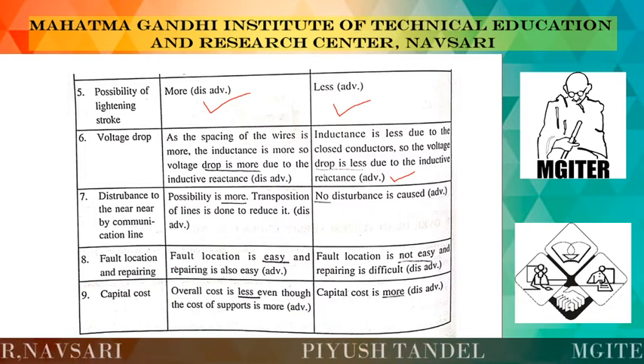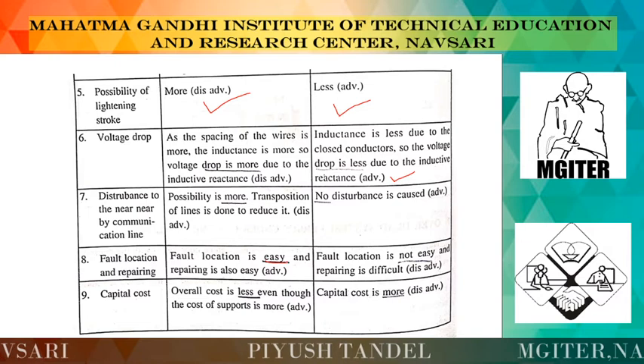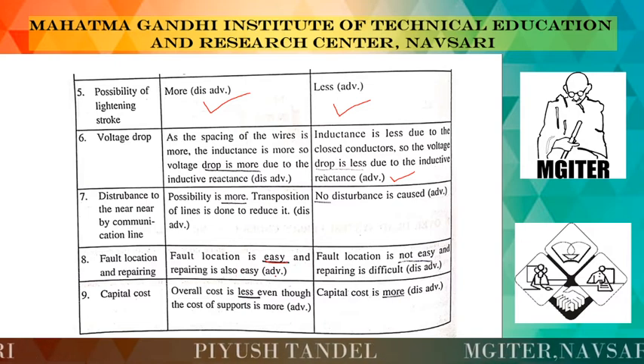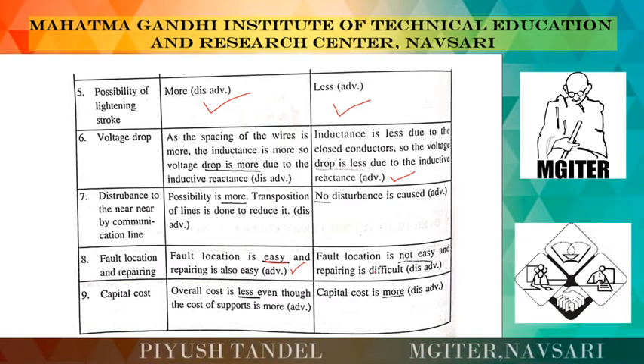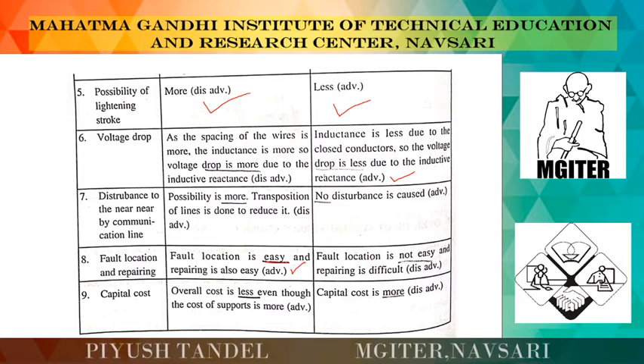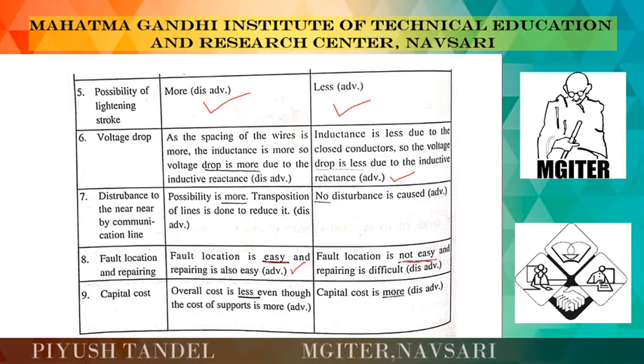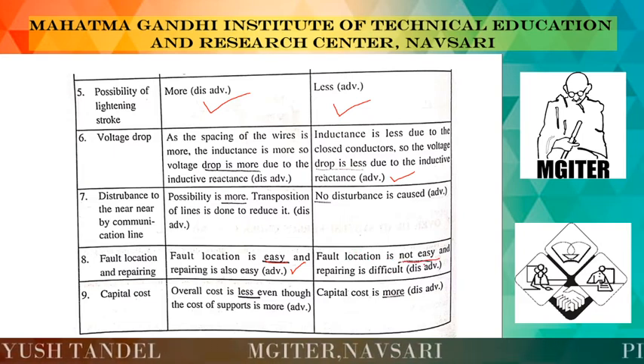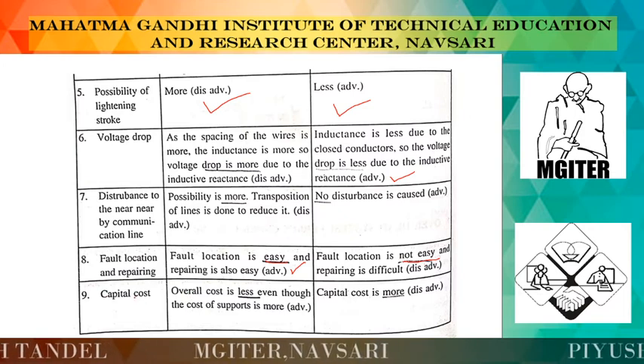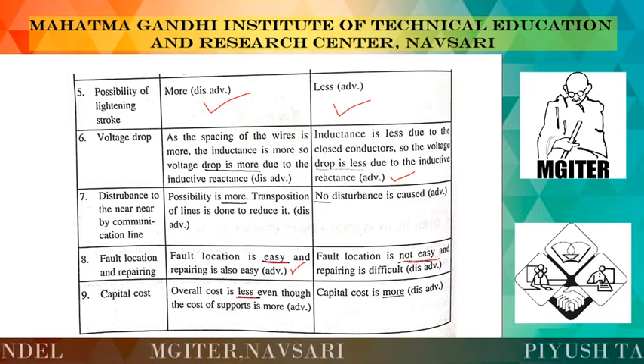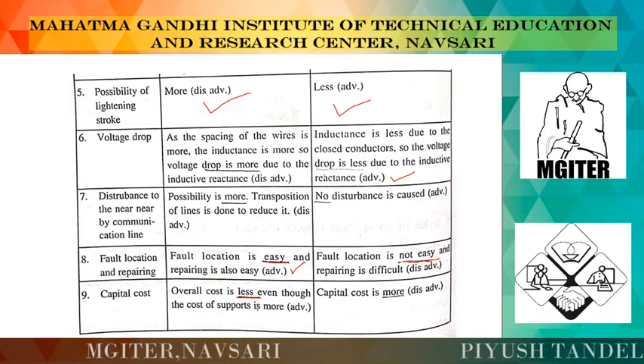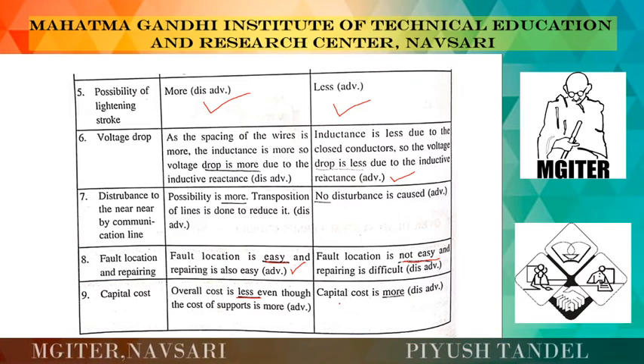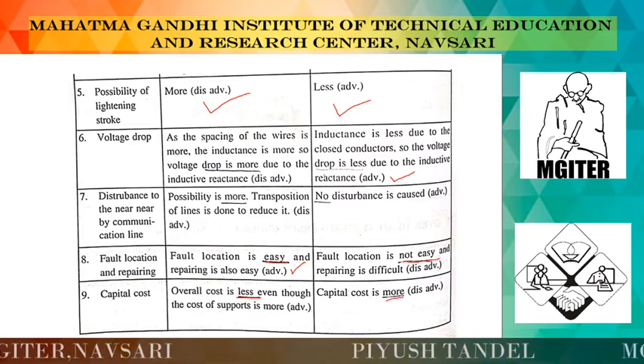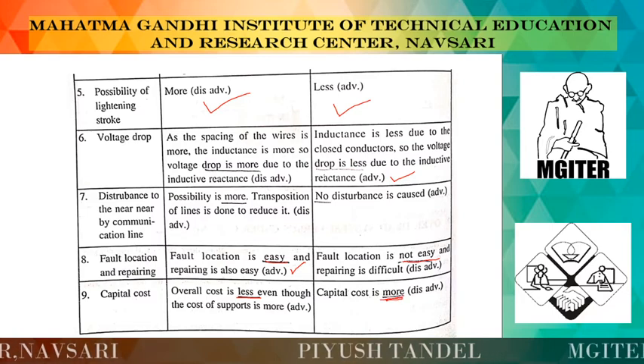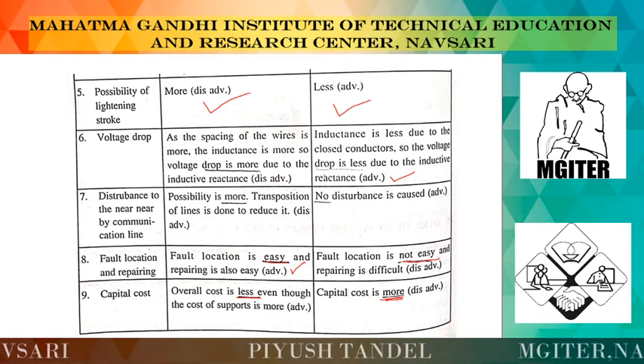Fault location and repairing: fault location is very easy, and repairing is also very easy, and those are the advantages of the overhead system, while fault location is not easy and repairing is very difficult for the underground system. And capital cost: the overall capital cost of the overhead system is very low, even though the cost of supports is more, and the capital cost of the underground system is very high because we are using cables.